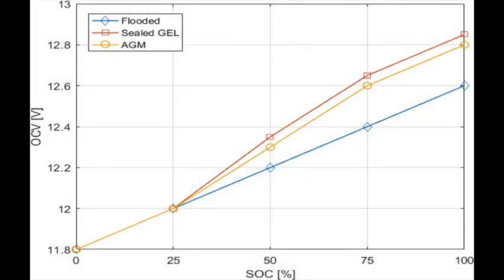However, all lead acid batteries, flooded, sealed, gel, or AGM, should never be discharged below 50% of their capacity, otherwise you risk damaging the battery.